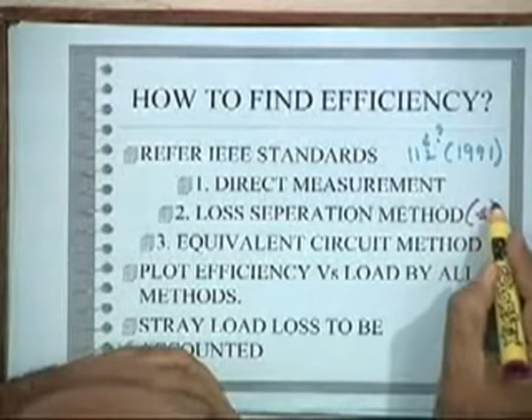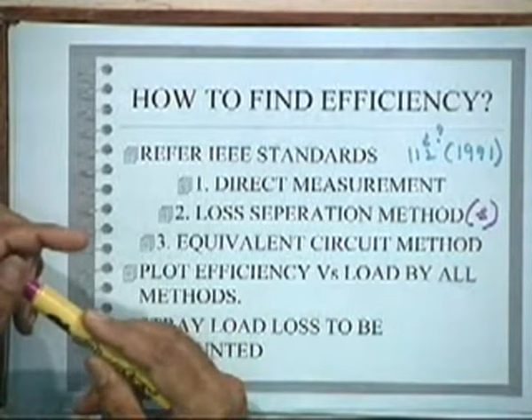But for that you need to have an accurate, one critical issue is you must know accurately what the slip is. Measurement of slip is the most difficult thing in an induction motor for two reasons. What is the slip? Slip is the difference between two speeds. One is synchronous speed, another is actual speed. So, the difference between two big quantities, 1500 minus 1480, errors are big, because there will be a lot of error. Even a 5% error in any one measurement will give rise to much larger errors in the slip. So, the slip measurement is a problem. Another quantity you are not sure about is the frequency. Supply frequency may vary. For 50 it may become 51 or 49, then again your measurements are wrong. So in actual measurements you will face this problem. Okay. So these are some of the issues you must be concerned with.